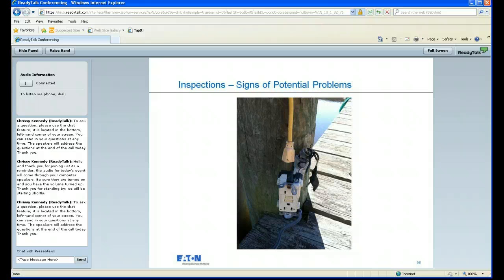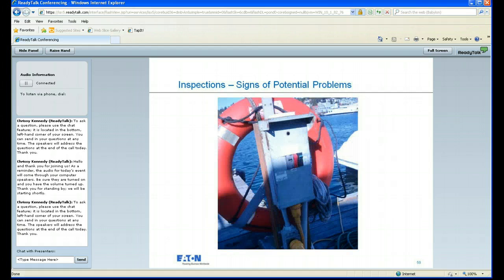I'm not really sure what this is. There are so many things wrong with this picture, I don't really know where to begin, but the installation itself appears to have some issues with it. There's also damage to the receptacle. GFI receptacles built like this should not operate if they've been damaged, but it's something that needs to be looked at when you're doing your walkthroughs.